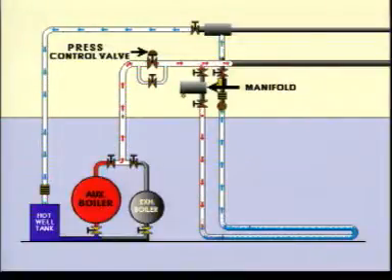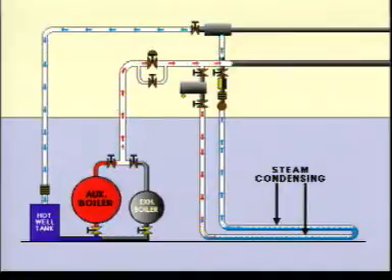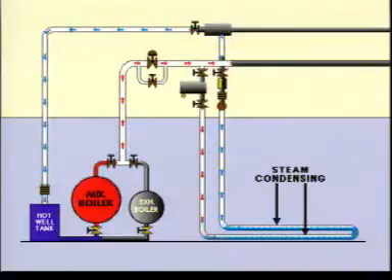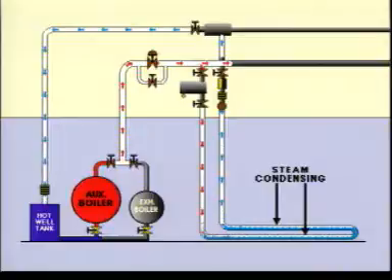You will get the best heating when the steam condenses to water in the horizontal part of the coil. Here, the steam cools below its evaporation point and condenses back to water, the heat being absorbed by the oil around the coils.